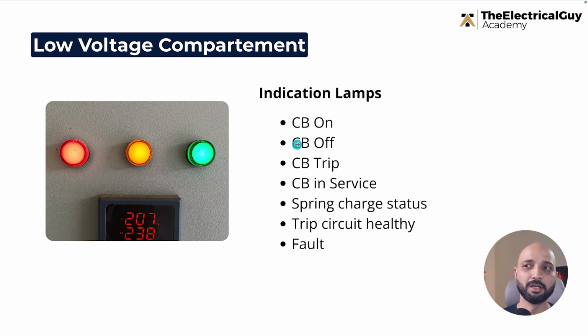Now the next question is, how do we get these indications? Let's take the example of the circuit breaker. The circuit breaker will have an auxiliary switch, which changes the position of its contacts based on the circuit breaker position. If the circuit breaker is on, a few contacts will be in the on condition. The moment the circuit breaker closes, the open contacts will close, and the moment they close, we can have the indication here. So we don't give 36 kV here again. We work based on the auxiliary switch and the auxiliary supply that we have inside the switchgear, right? So indication lamps are very useful things to indicate the status.